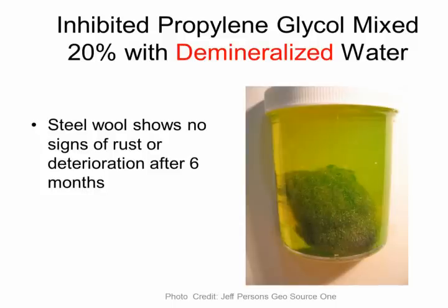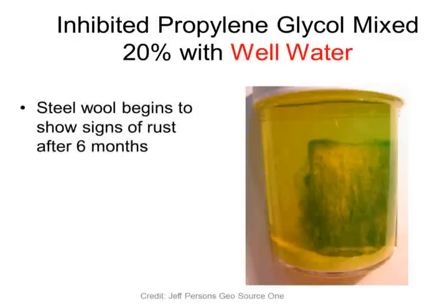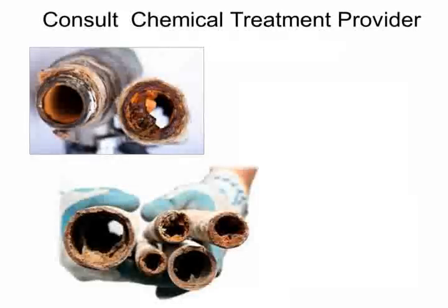Now, pull the demineralized water out and put in place well water, repeat the experiment, and here's what you get 6 months later. You can see the steel wool starting to break down. It's oxidizing. And down here in the bottom of the beaker, you can see the inhibitor starting to precipitate out, basically rendering the antifreeze characteristics of your glycol to protect that geothermal system or that snow melt system from the effects of freezing. And that's a really bad problem.